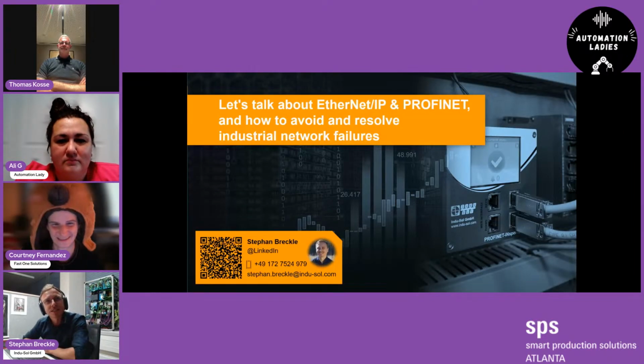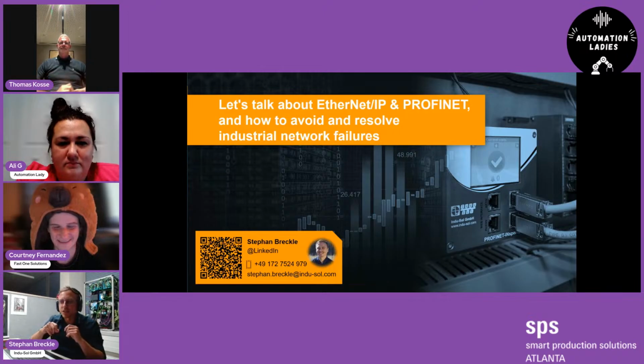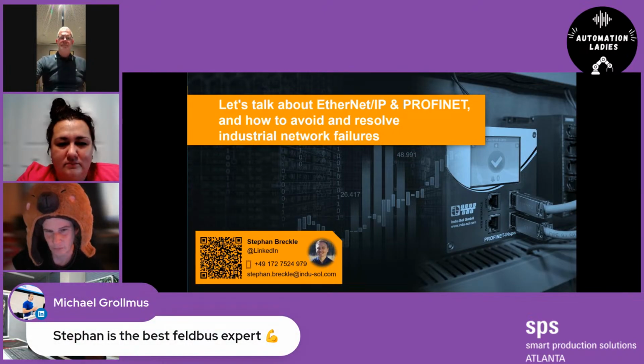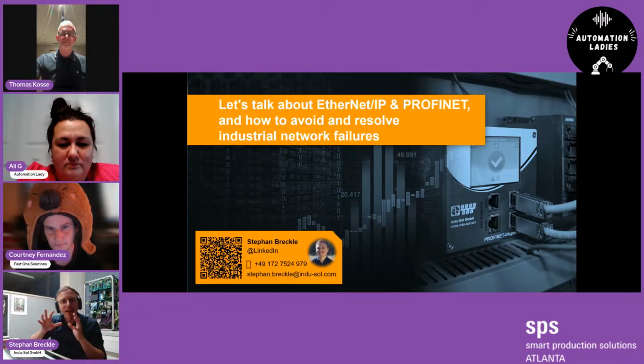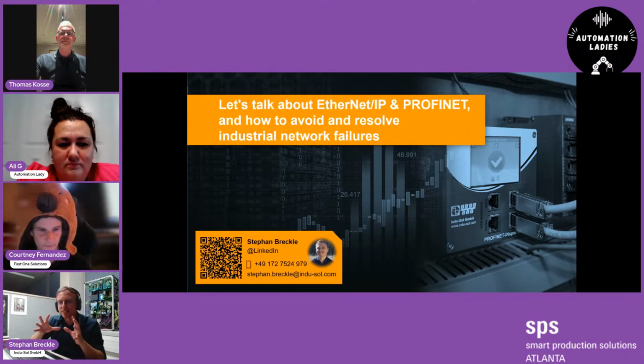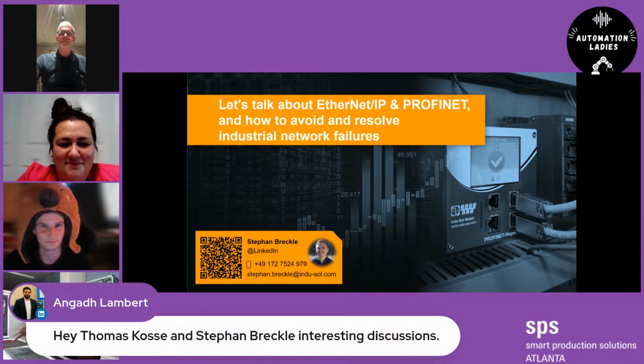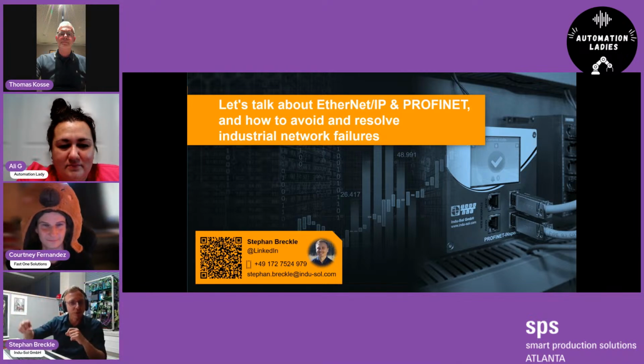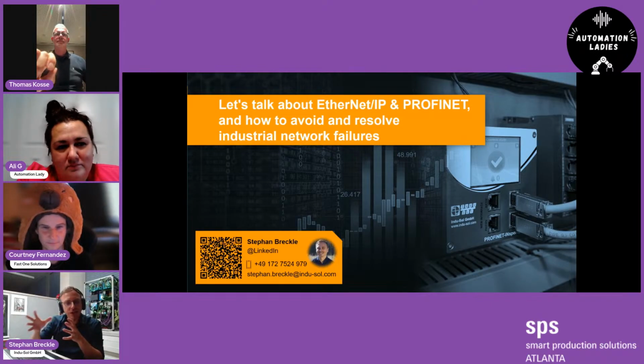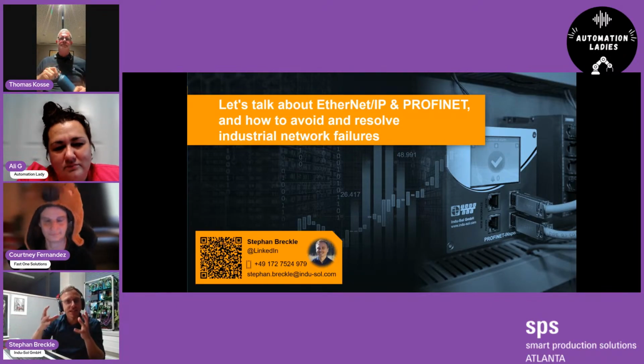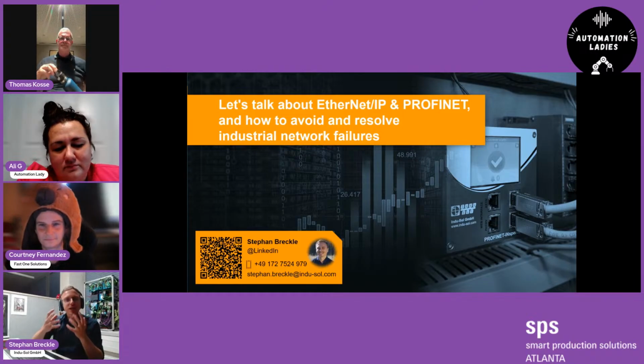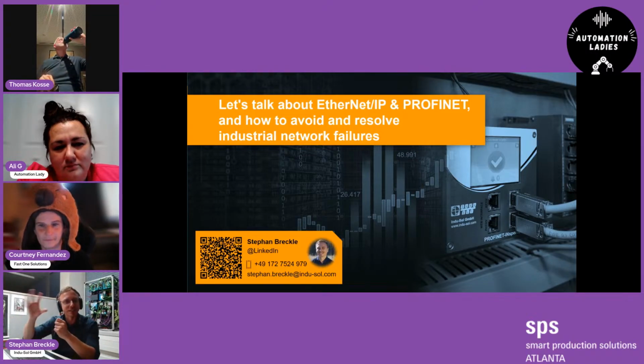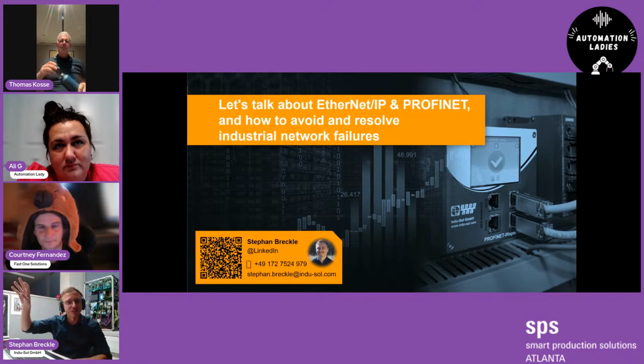If you run Ethernet IP or PROFINET, normally to analyze the device, or how the communication runs from the PROFINET point of view, you get a diagnostic if something is going wrong. If your device doesn't communicate, you get a diagnostic. But the diagnostic only tells you the communication doesn't run well, it doesn't tell you the reason. You can only expect the device to swap the LED to red, and your diagnostic buffer tells you something is wrong on this device.